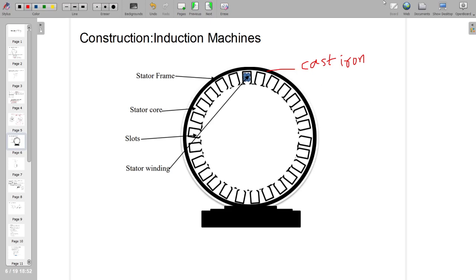The stator core is built up of high-grade alloy steel laminations. A large number of thin laminations are stacked together. The stator core provides housing for the three-phase stator winding and also forms the path for the rotating magnetic field. To minimize losses, the laminations are very thin — approximately 0.35 to 0.65 mm each.